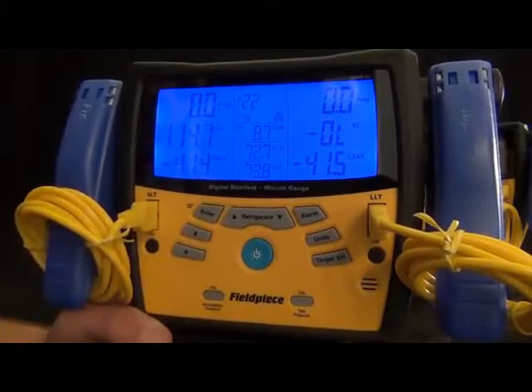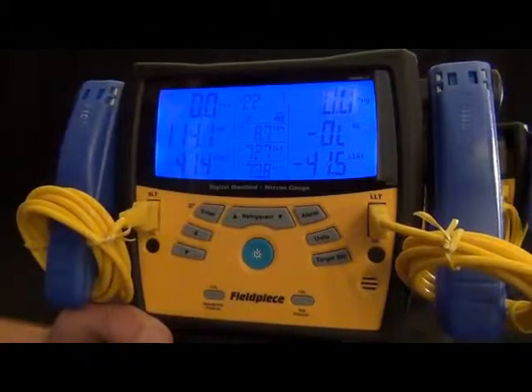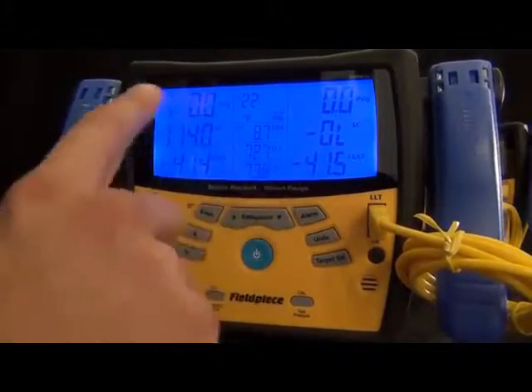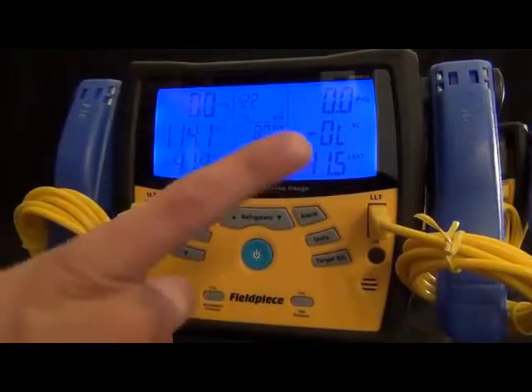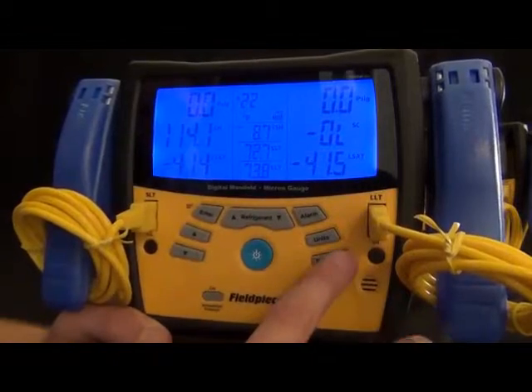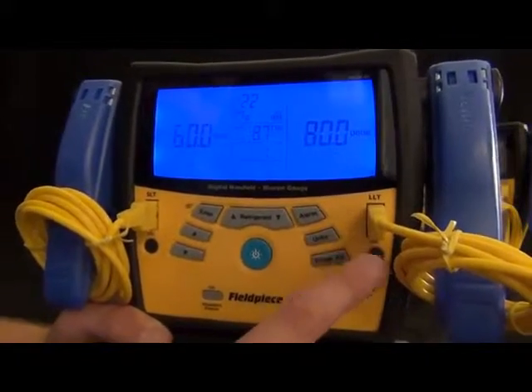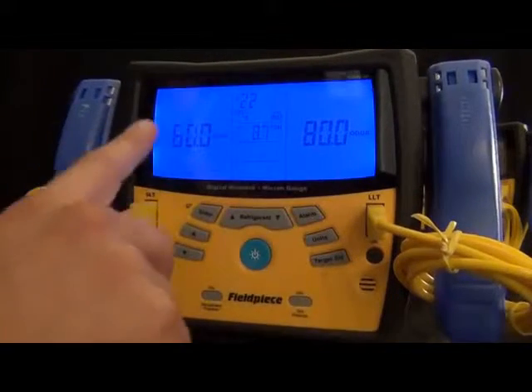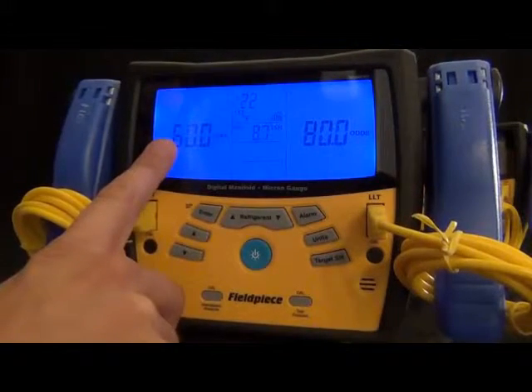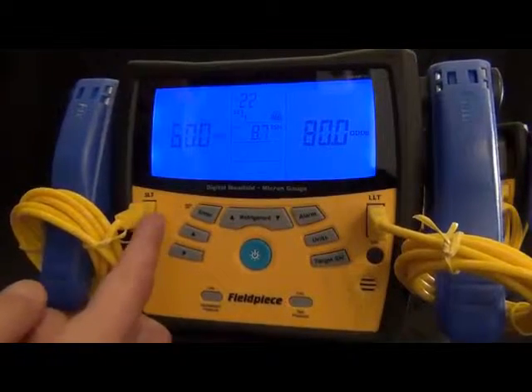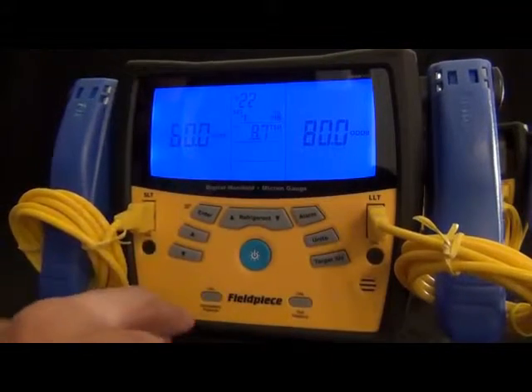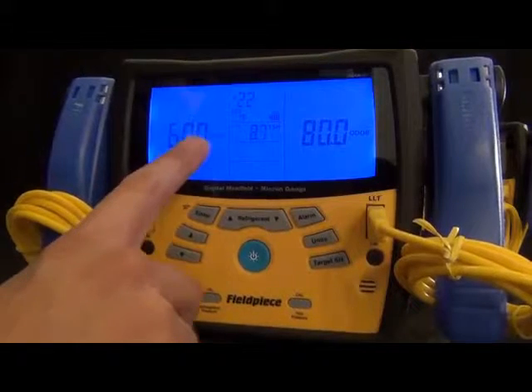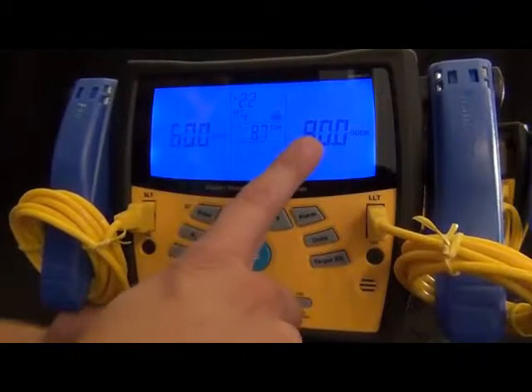The other mode is target superheat, and this is for your indoor wet bulb and outdoor dry bulb. These can be entered manually or measured with the included thermocouples. In this case, I put 60 degrees in for the indoor wet bulb and 80 degrees in for the outdoor dry bulb, and it will calculate a target superheat of 8.7. This is for getting target superheats for fixed restrictor systems.